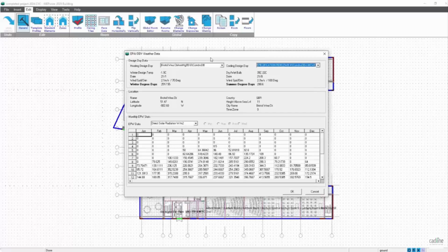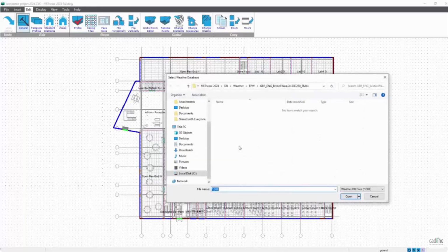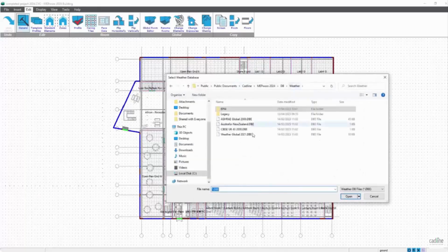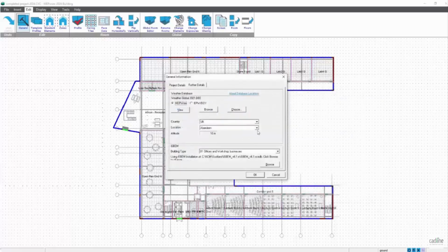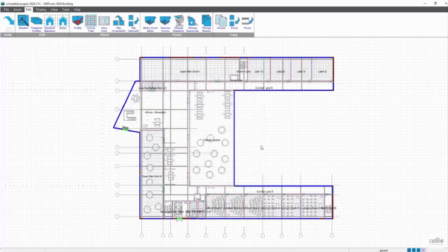You could apply the same for the heat loss. However, to do the heat losses, you might find it quicker just to hop back to the MEP Works to do the heat loss calculations. Pick up the existing weather database that you've used in the past. Pick in this case your Bristol location. And then when you do the energy calculations, in the edit general plant, put in your -4, -5, -10 degrees.